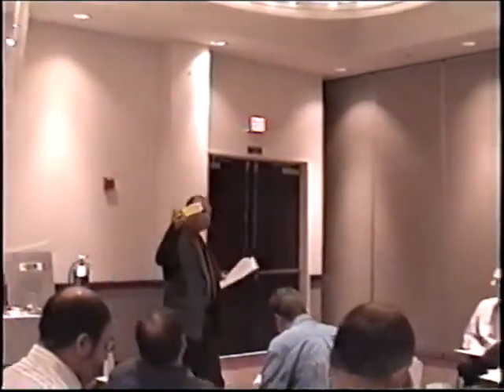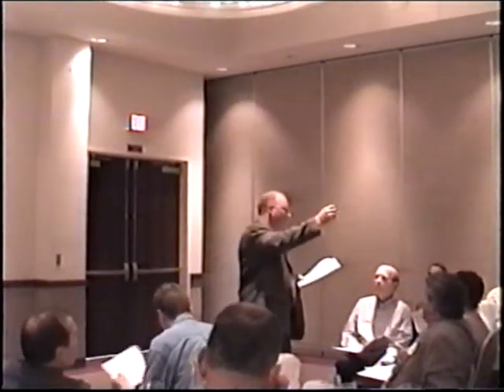after the UL300 came out, we started putting these on, and this was mainly for the insurance and for the authorities having jurisdiction. I'm sure, Kim, I don't know if you've seen any of these on any of your boxes yet, but we've taken a step by putting these on the front of our customers' boxes that we're servicing to make sure that people know that their system isn't UL300. So all the dry chemical systems that are not UL300, and then the liquid systems that are non-UL300 are getting these stickers put on. We started with dry chemical, now we're looking into the liquid systems.